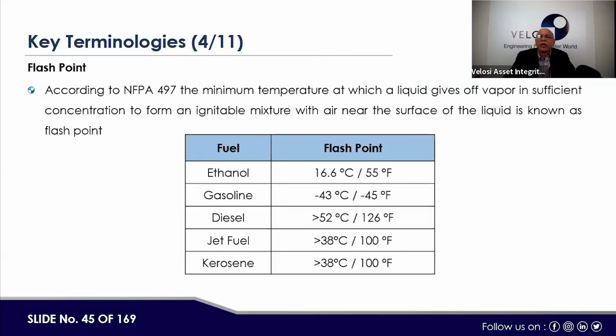And then gasoline is at minus 43 degrees C. Diesel's flash point is above 52 degrees C. Jet fuel is above 38 degrees C. Kerosene is above 38 degrees C. Whereas ethanol, or normal alcohol, has a flash point of 16.6 degrees C. It means it can catch fire easily in summer.